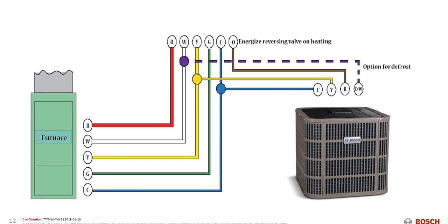On a gas-fired furnace, here's a way that you could wire it up. Remember that I need a simple fossil fuel thermostat at this point, making sure that the gas-fired furnace and the outside heat pump do not work simultaneously. Dedicated C, give me a B for the reversing valve, a W wire for the defrost, and a Y wire for my compressor, and it will work like a champ.